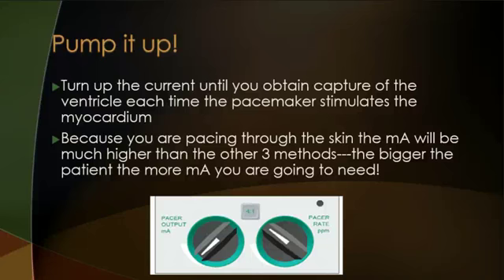If that's not right, turn it up to 70. Because you're pacing through the skin, like I said, you're going to need much higher than epicardial, much higher than transvenous, much higher than transthoracic. The bigger the patient, the more mAs you're going to need.